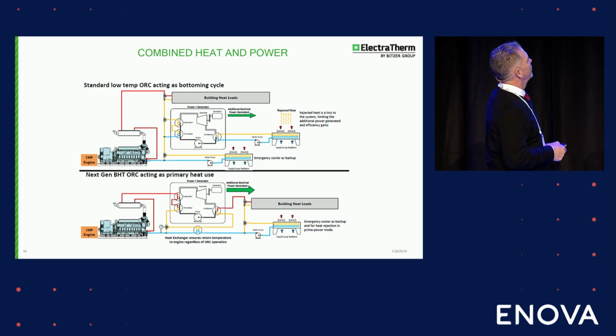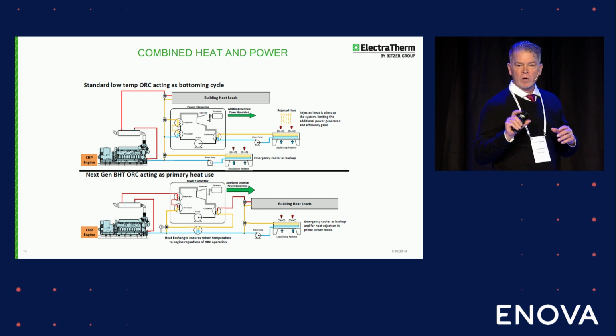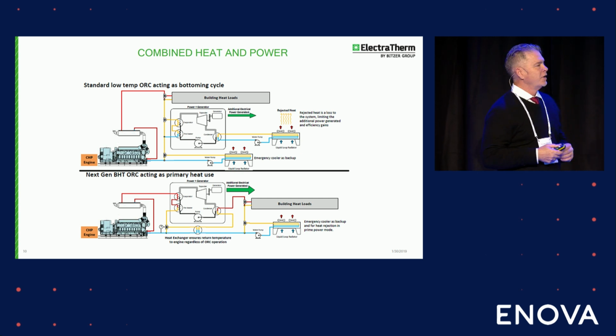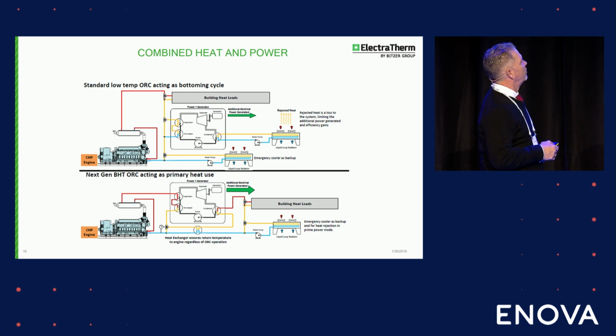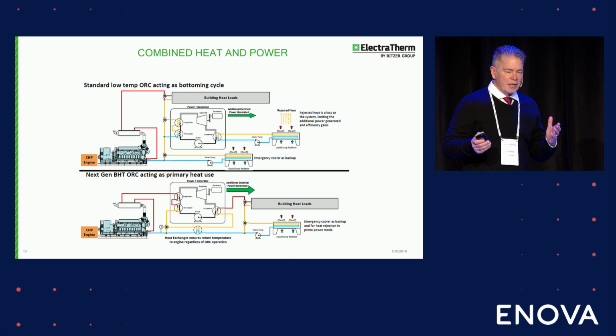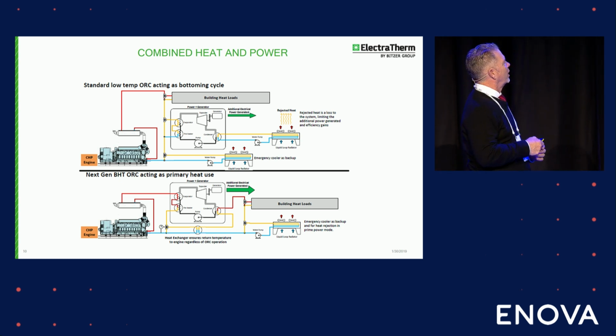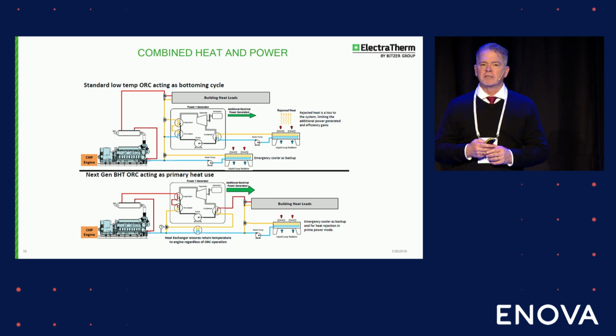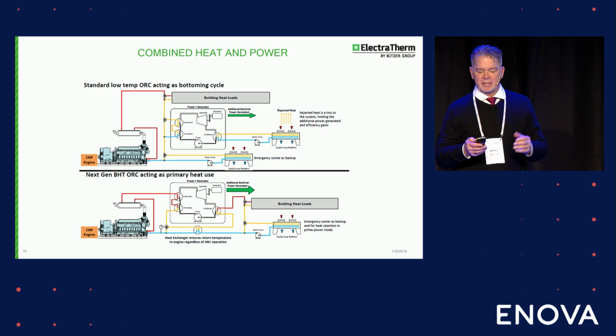It goes from a liquid to a gas across this stage, then across our expander, which is a twin screw compressor in reverse, and that drives a generator, giving us electric output. Then we condense it back from a gas down to a liquid. This is all inside our box. So when we install at a location, it's literally hot water in, return to the source, heat up, and this is a closed loop—we've got a closed loop inside the ORC, and then a condensing loop. That's really as simple as it is. So we deliver a pretty turnkey system that way.